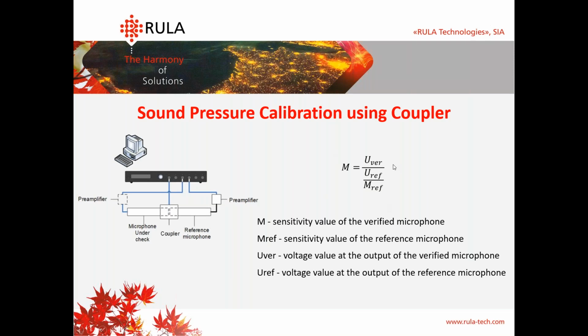Here you see the main formula for this. The sensitivity of the microphone which is being verified is calculated by dividing the voltage value at the output of this verified microphone by the voltage value of the reference microphone divided by its sensitivity. It's the main formula for this. And after that, we calculate the deviation according to the values on the base frequency.